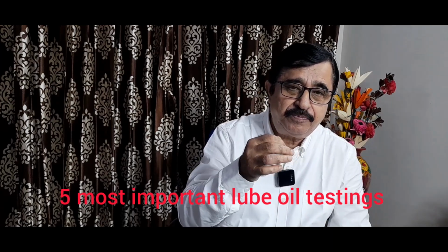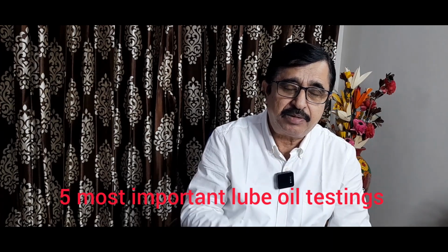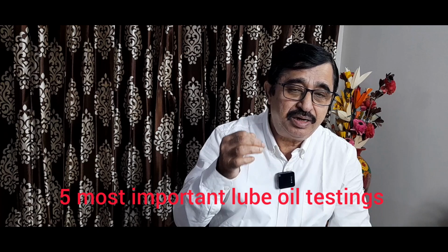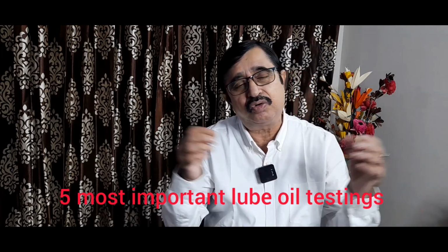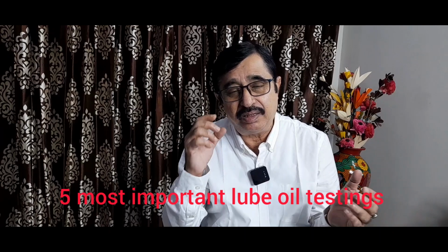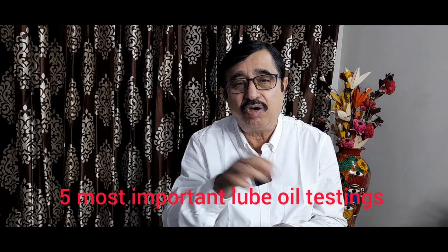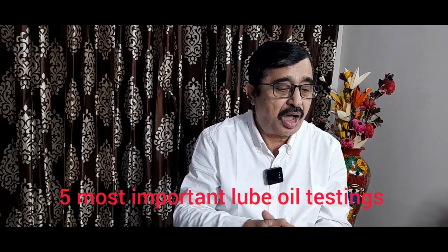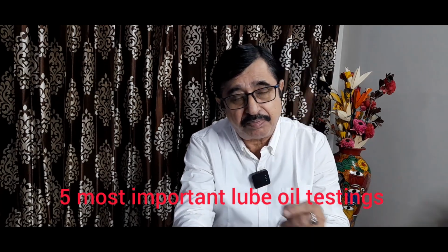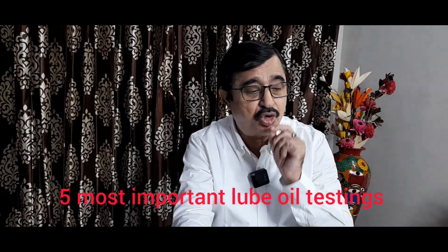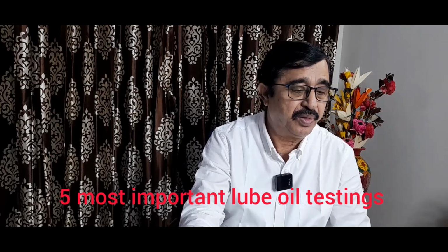It may come from lube oil cooler leakage, from gland seal steam leakage, and from the outside if your lube oil tank is not properly sealed or breathing is not there. So high water content may damage the bearings and the rotating equipment of the turbines.